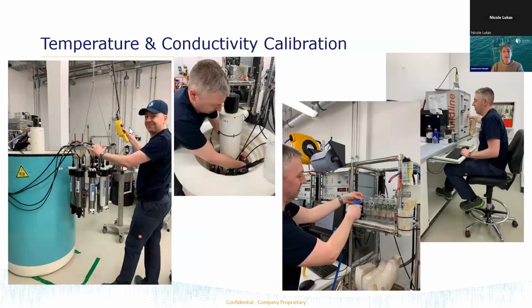The next step in the process is temperature and conductivity calibration. So what we're looking at here, again, is our lab in Kempton, but it's very similar. We have baths that are calibration baths that are a proprietary design. So we've created these and used these for many, many years. But the idea is that we have either natural seawater that we collect off the coast of Hawaii. So some instruments are calibrated in true seawater. Other instruments are calibrated in a saltwater brine. The large baths there, actually the saltwater brine.